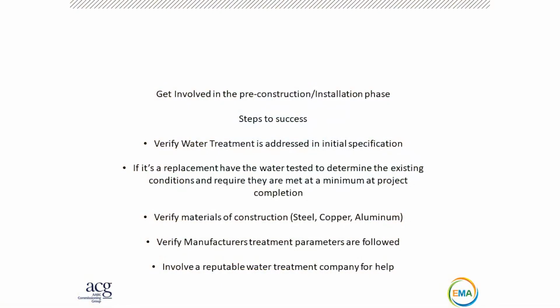Okay? So boiler design, the most important thing everybody here can do is get involved in the pre-construction phase and the installation phase. Your facility's putting in a new boiler plant, you've kind of given the job to somebody else to handle, and you walk in and you take it over day one when they turn it on. Was everything done properly? Was it treated properly? Were the boilers boiled out properly? Was the piping cleaned properly? We don't know. So it's extremely important to make sure you get involved with that. Normally there's a submittal or a specification to have a water treatment company involved, usually through the mechanical contractor or someone like that, the boiler installer. Make sure that's completed. Usually it's buried on page 50 of a submittal, and most people miss it.